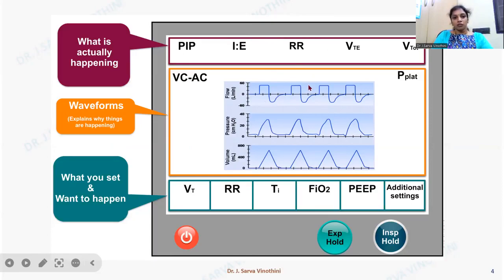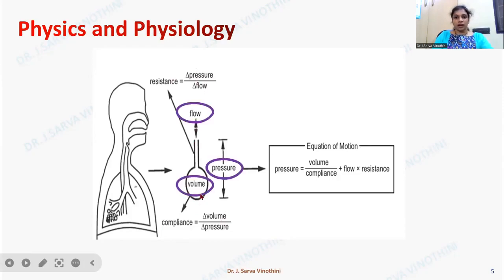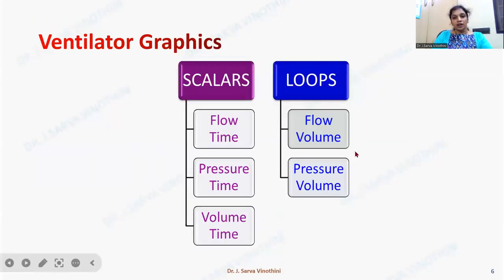Understanding ventilator waveforms and graphics explains why things are happening the way they have. Respiratory physics and physiology revolve around two main concepts: resistance and compliance. Resistance is determined by the flow of air through the airways, and compliance is determined by the distensibility of the lung. In ventilator scalars and graphics, we monitor three parameters mainly: flow, volume, and pressure — and use these to assess resistance and compliance using the equation of motion.